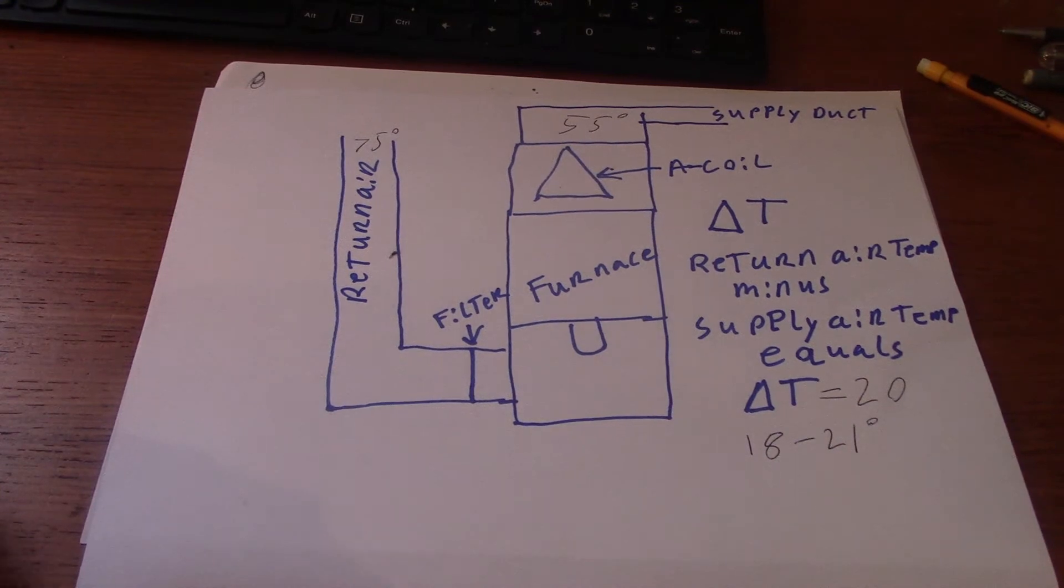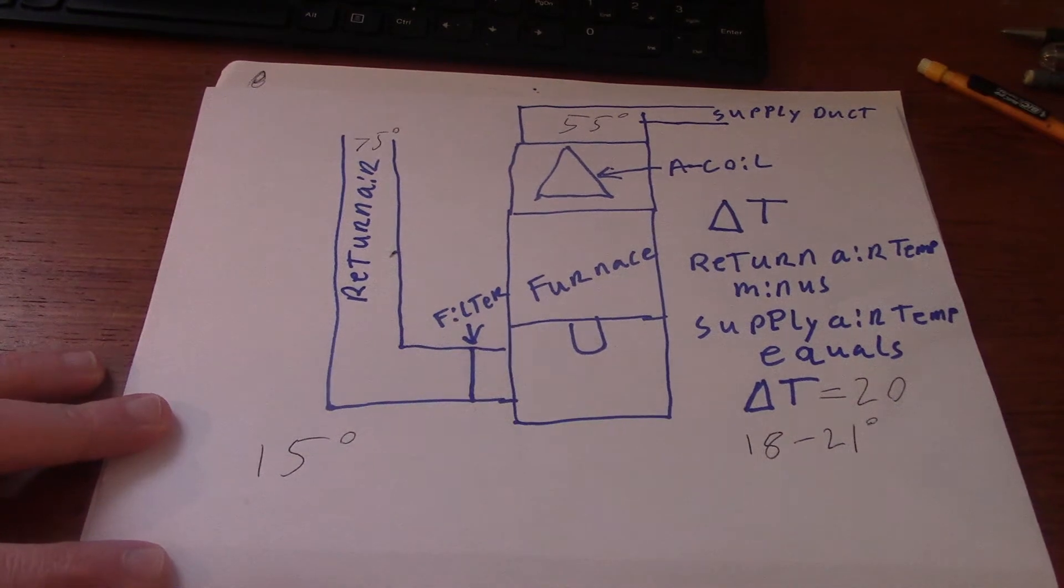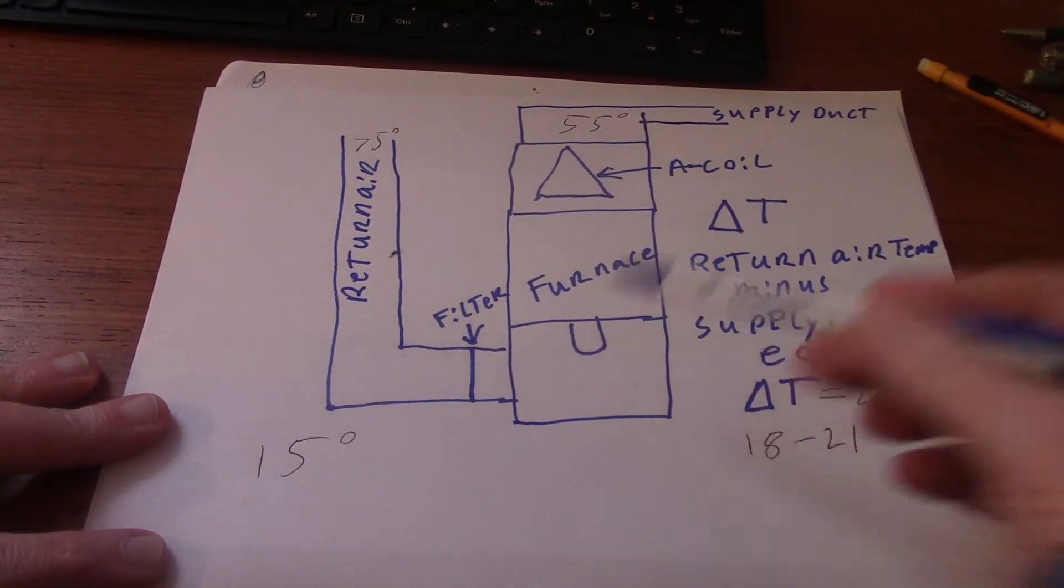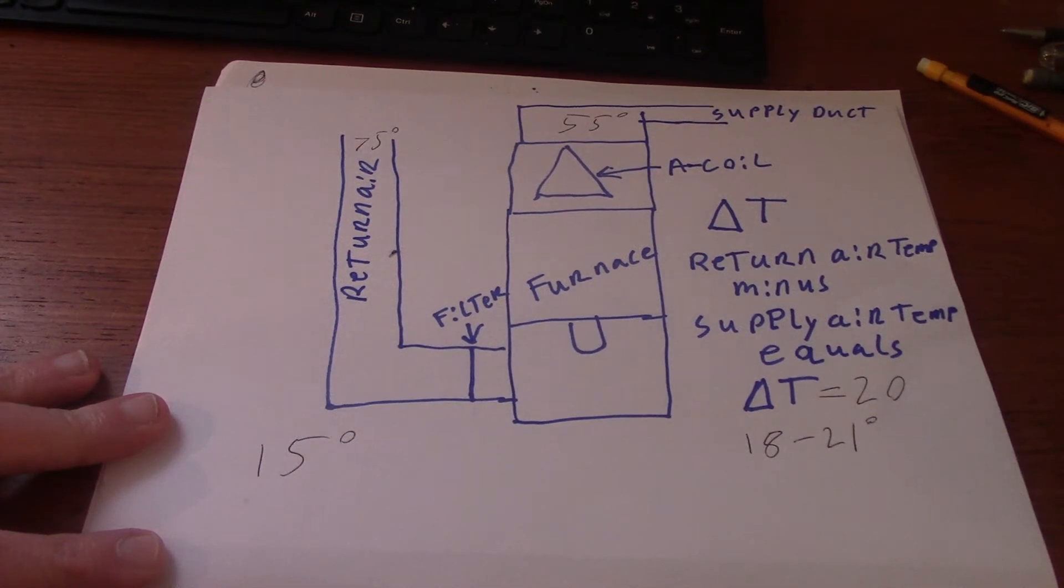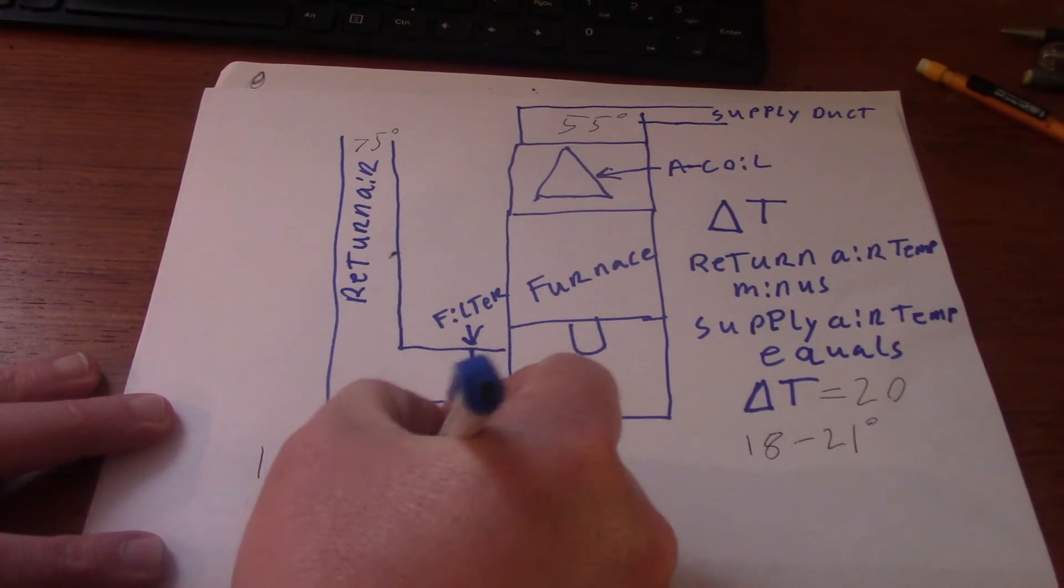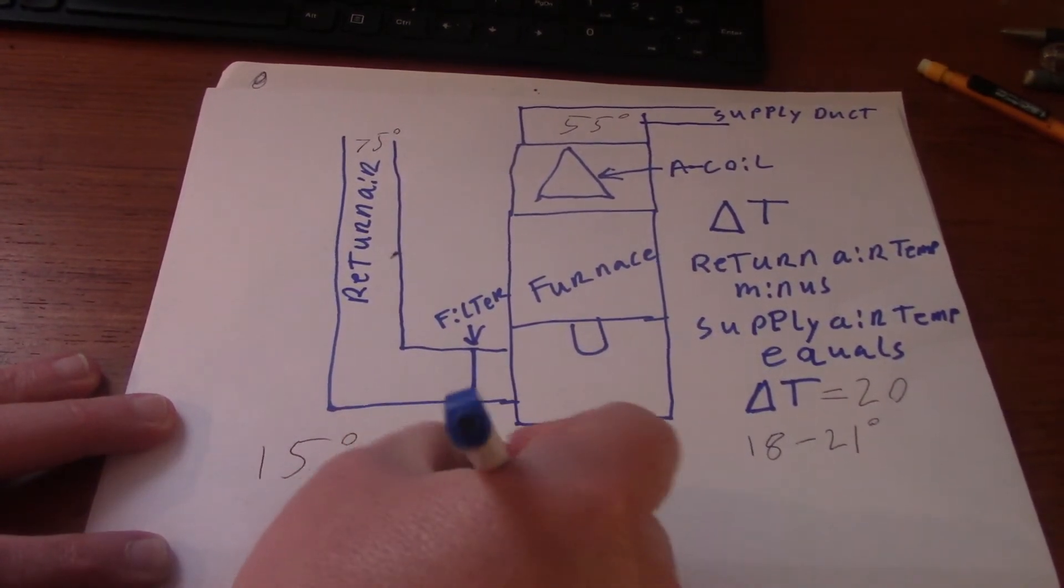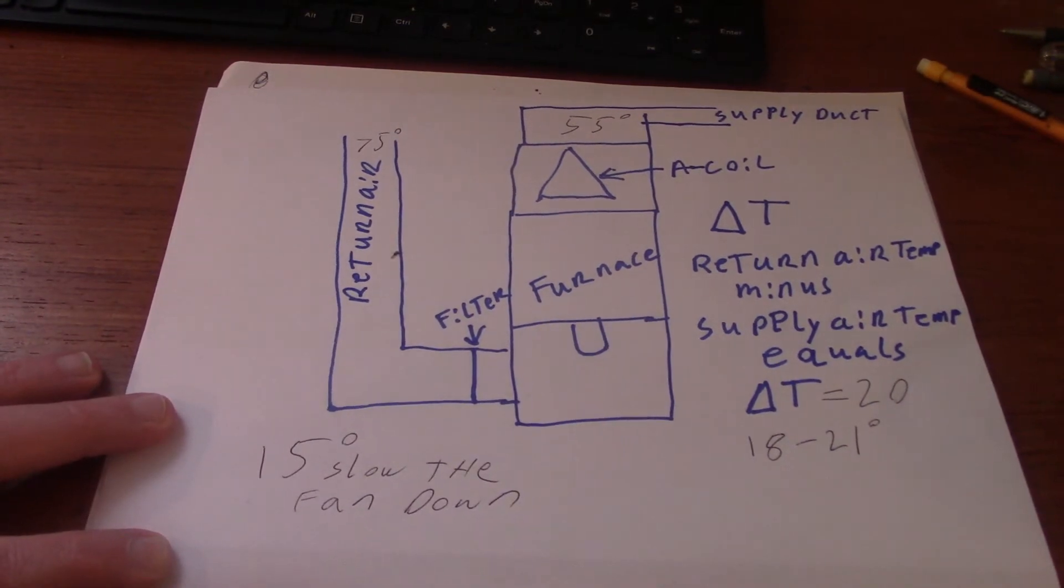If you have Delta T that calculated at, let's say 15 degrees, the blower speed on the furnace here, the fan, it's moving too fast. You're moving too much air. The evaporator here, your A-coil, cannot absorb the heat to function properly. The air is going by too fast. So you'd have to slow the fan down. That's if you're at 15.